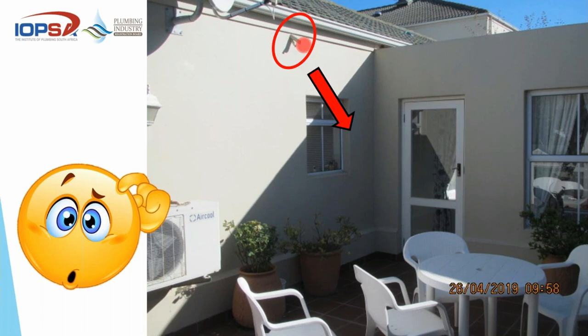And by the way, this was a geyser replacement, and this was the original position of the TP discharge. So the plumber didn't install the TP discharge there. He just neglected to move it. Whether it was noticed or not, I don't know, but he neglected to rectify the dangerous situation. The tray overflow is fine. I mean, let's be honest, if something leaks and it drips down there, so what? It's fine. But the TP discharge is not safe.